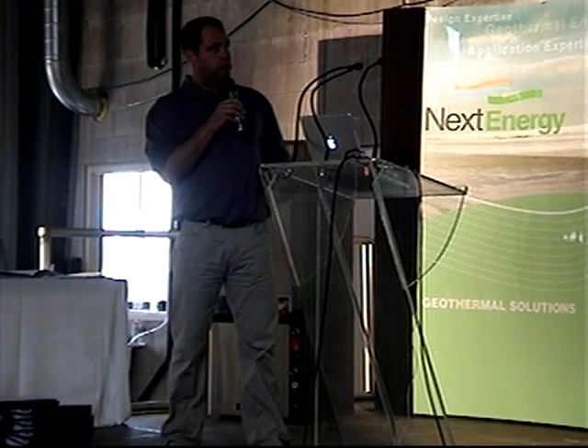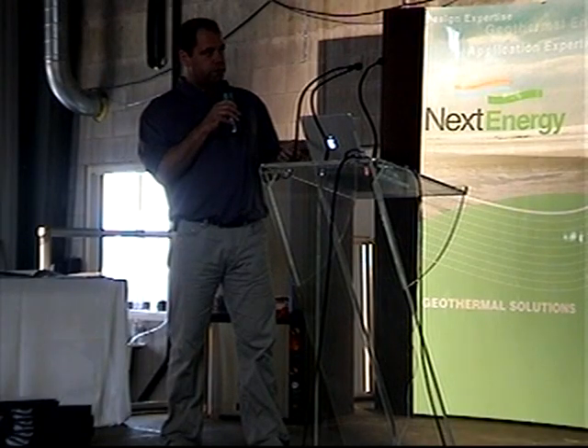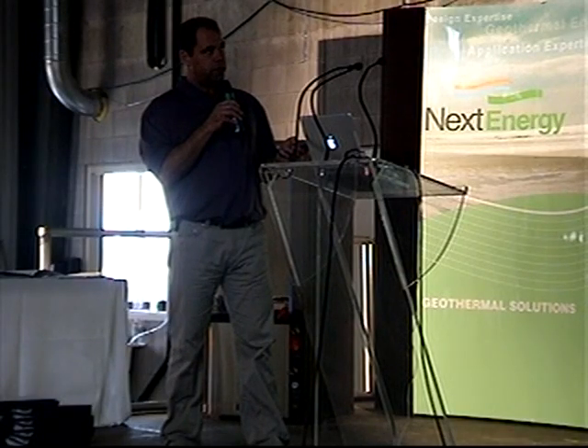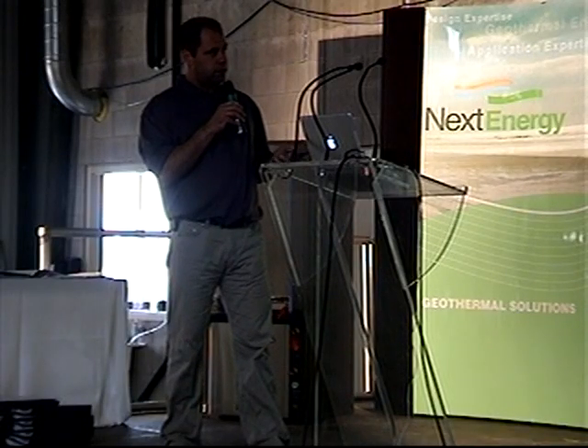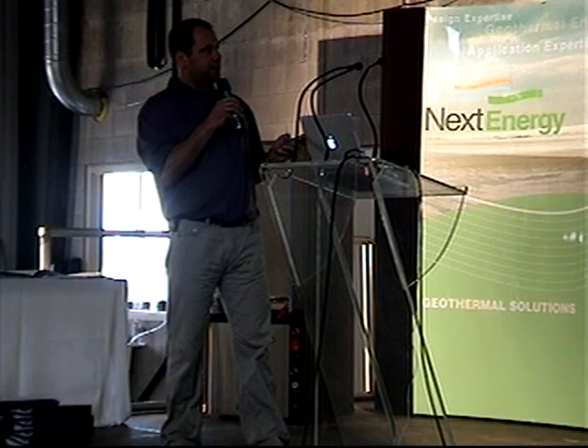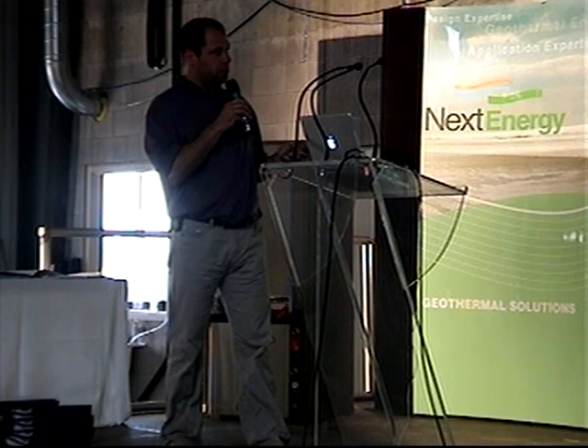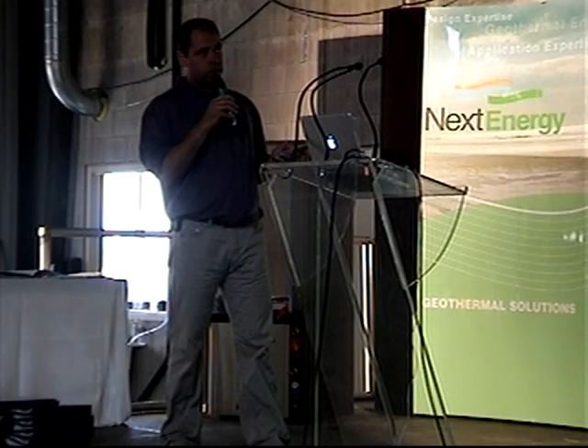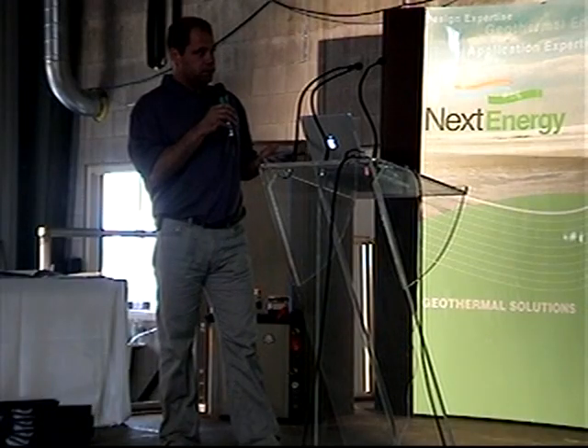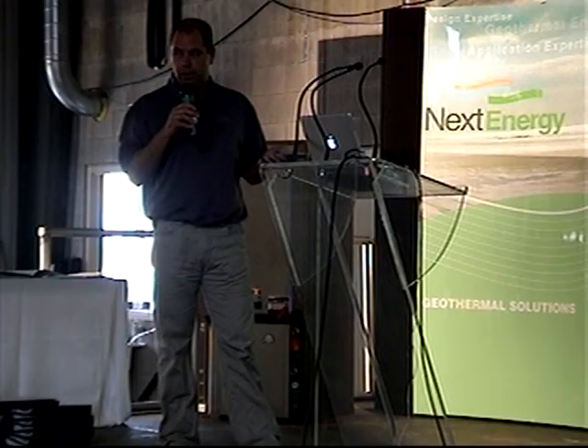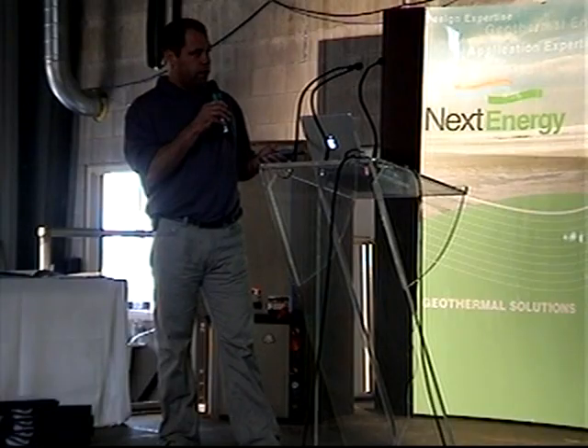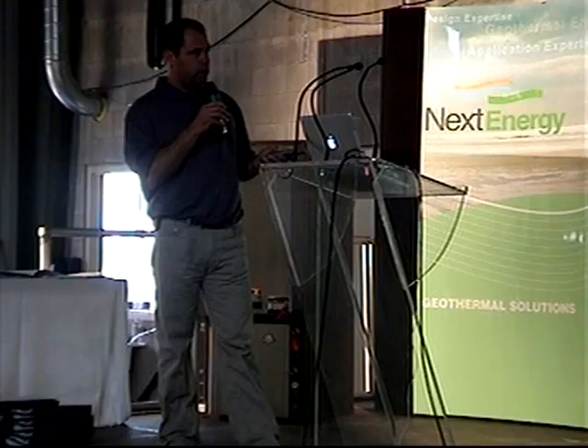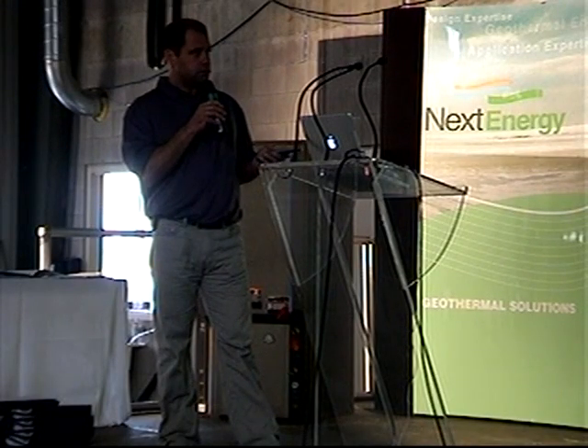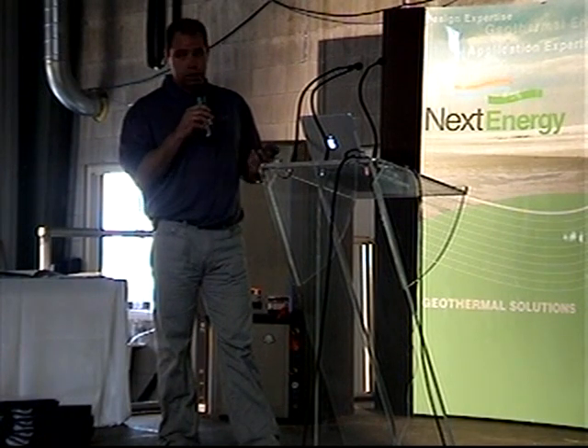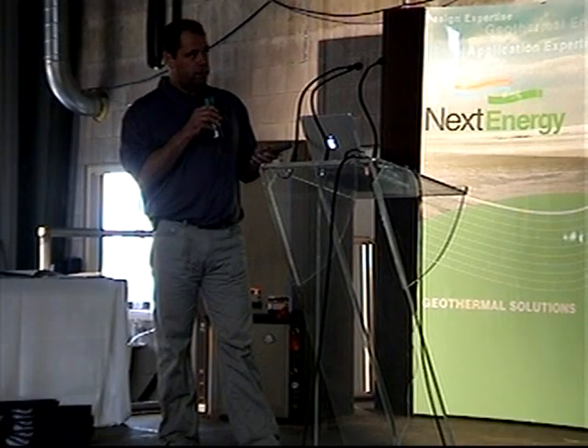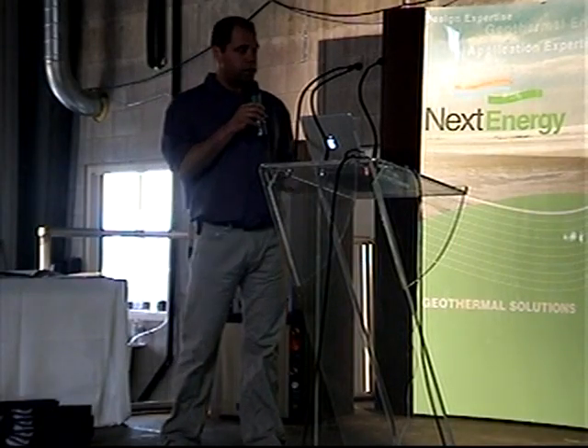All right, here's a basic unit running in a heating cycle. Start off with the compressor, through your de-superheater, into the reversing valve. From the reversing valve, comes down, this heating cycle, sorry, into your air coil, which is your condenser. That's where you're getting the condensing, again, that's rejecting the heat. It's going from a hot vapor into a, we'll say cool, not actually cool, probably about an 80-degree liquid. As it comes out of that condenser, it's 100% liquid into the expansion valve. If it's not 100% liquid here, the expansion valve will not work. Through the filter dryer into your coax coil, where it's extracting heat out of the ground. That's now your evaporator, of course, and back into the compressor. That's a basic refrigerant cycle of a heat pump in heating cycle.